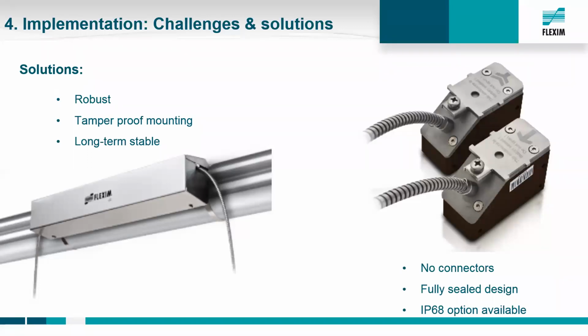The mounting has to be tamper-proof, robust, and long-term stable, because once it is buried, the transducers should stay in place and at the right distance you have commissioned them with. You have to ensure that small sediments, rocks, and parts at the filling process are not unlining the transducer. So we are coming with a rail.